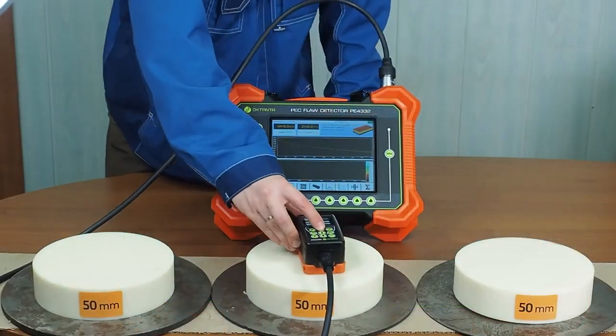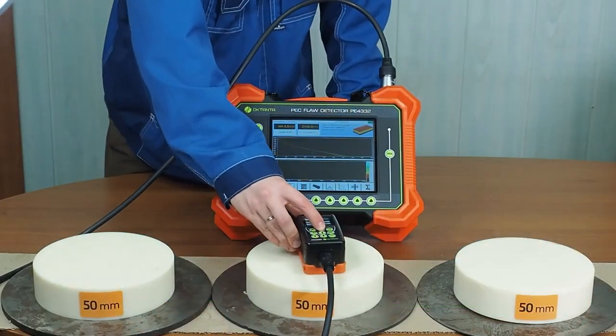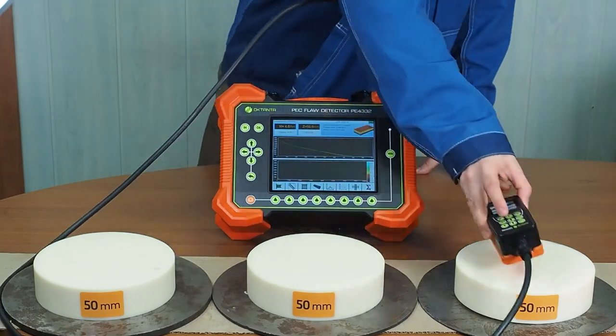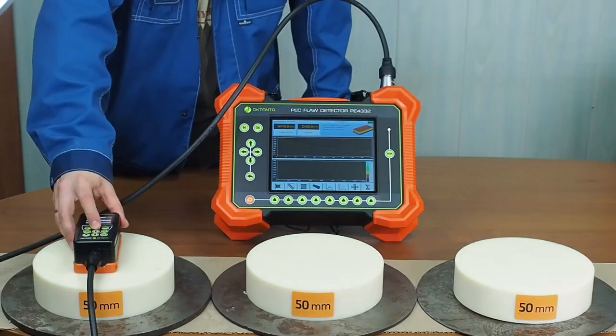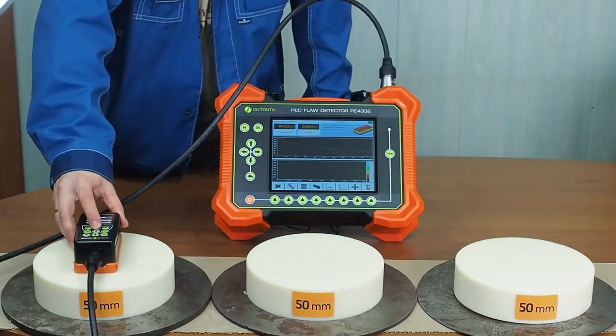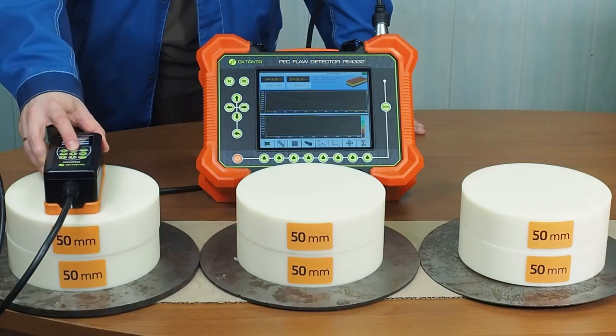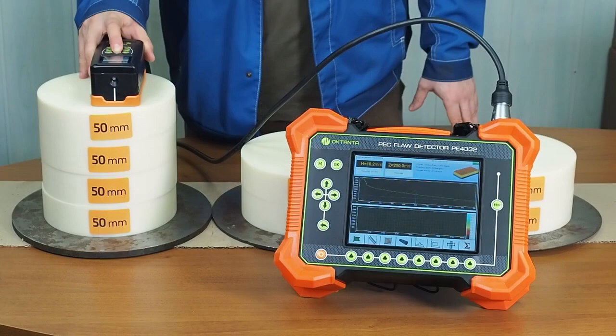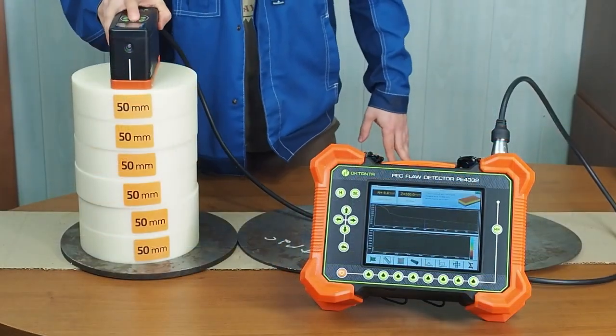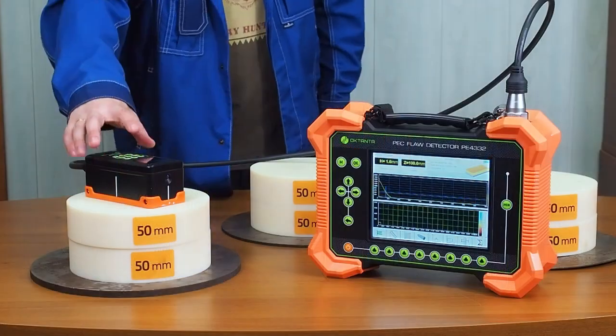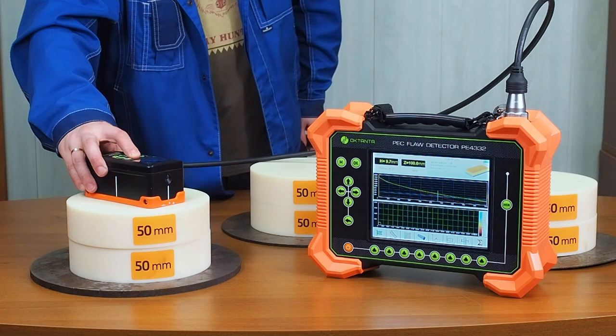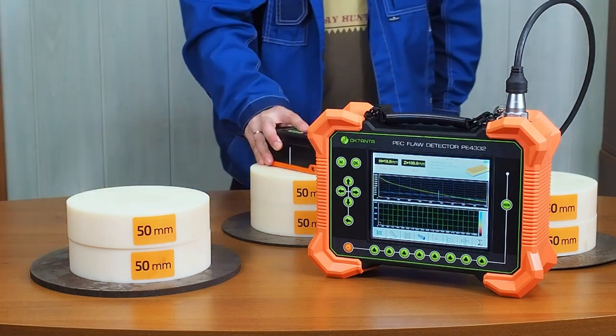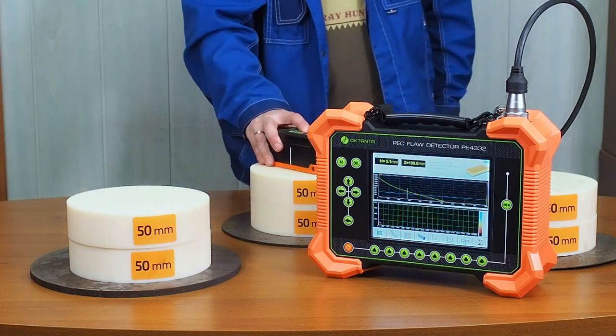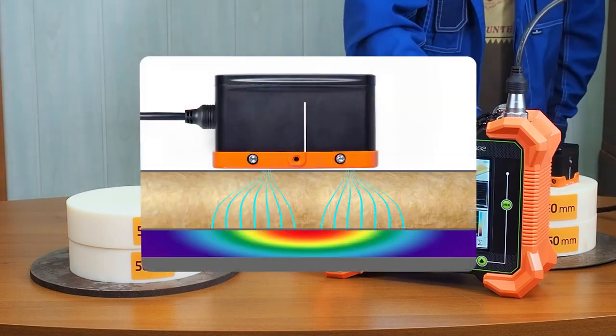To validate the method, let's measure test steel discs with thicknesses of 10, 5, and 2 mm respectively. The measurements will be carried out through insulation pieces with thickness from 50 mm to 300 mm. We'll check whether the device can see the difference in steel thicknesses of these three discs. After test pieces, we'll proceed with real pipes where casings will be installed in addition to insulation. Before taking measurements, let's talk a little about the method itself.